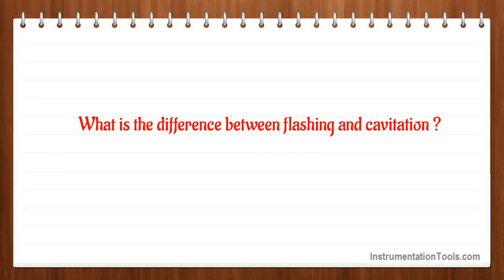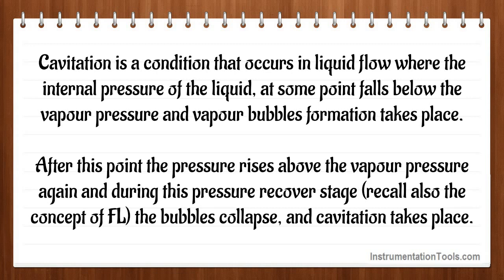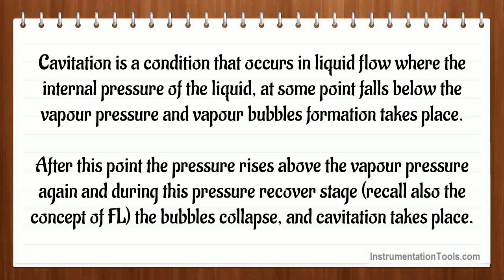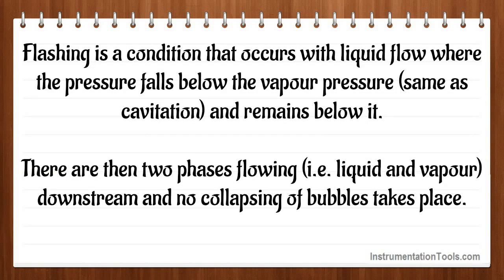What is the difference between flashing and cavitation? Cavitation is a condition that occurs in liquid flow where the internal pressure of the liquid at some point falls below the vapor pressure and vapor bubble formation takes place. After this point, the pressure rises above the vapor pressure again, and during this pressure recovery stage the bubbles collapse and cavitation takes place. Flashing is a condition that occurs with liquid flow where the pressure falls below the vapor pressure — same as cavitation — but remains below it. There are then two phases flowing, liquid and vapor, downstream and no collapsing of bubbles takes place.